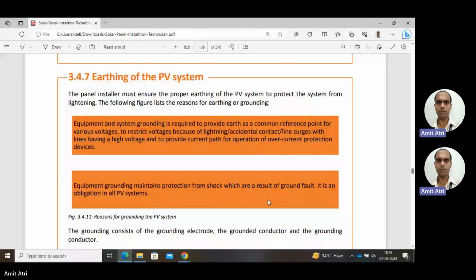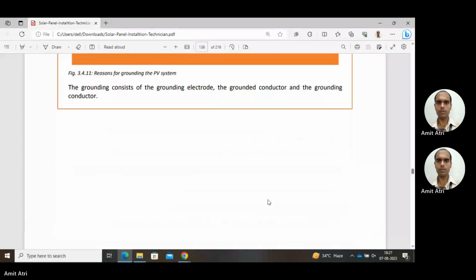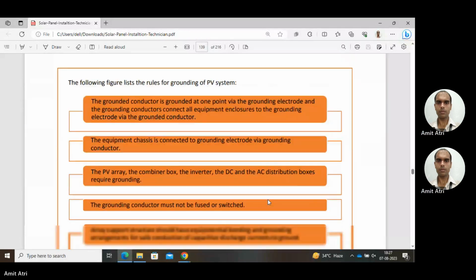So the next reason is that equipment grounding maintains protection from shock, which can occur as a result of ground fault. So it's also protection from electric shock. The grounding consists of the grounding electrode, the grounded conductor, and the grounding conductor. So, rules for grounding of a PV system. First rule: the grounded conductor is grounded at one point via the grounding electrode, and the grounding conductors connect all equipment enclosures to the grounding electrode via the grounded conductor.